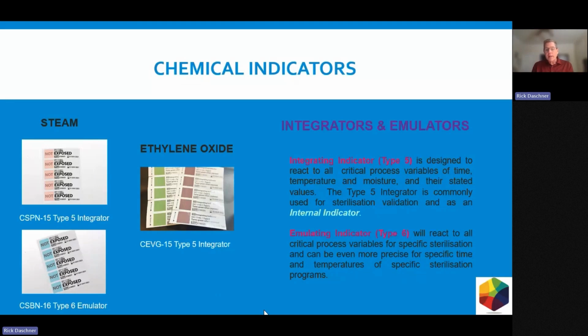And worldwide, type 5 seems to be the single most popular chemical indicator outside of the type 1 process indicators, because it is designed to react to all critical variables of time, temperature, and moisture, and their stated values. So the type 5 indicator is commonly used in sterilization validation as an internal indicator. So you put this in an area where it might be within a load somewhere, or multiple loads. You may put one in every package you put into a load, to ensure that particular package or product was sterilized properly. And again, probably the most popular chemical indicator that we sell.